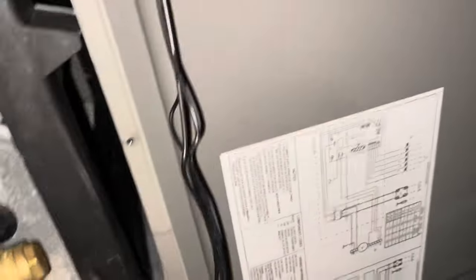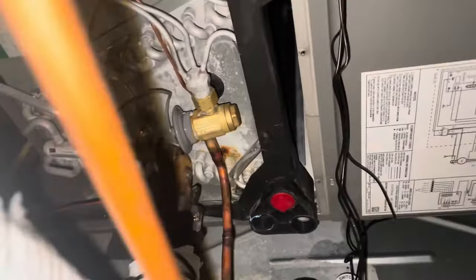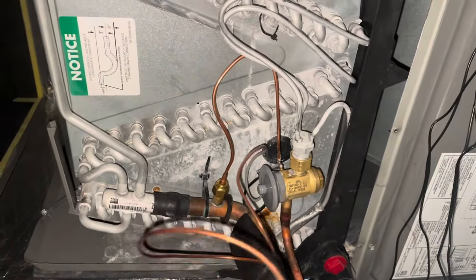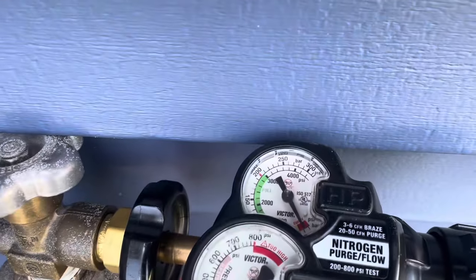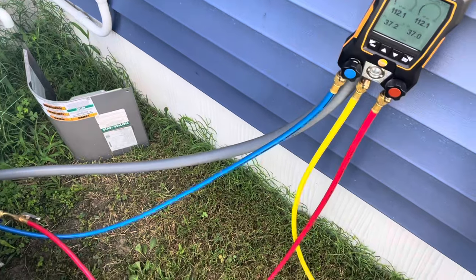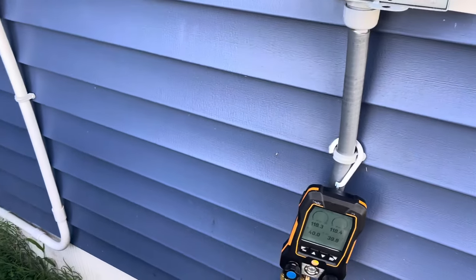We'll take our putty back off and get it mounted. We're brazed in, looks pretty good. Got this hooked up — we're gonna put it on pressure and make sure everything holds. Still gotta hook up the bulb. Pushing this back in there, securing everything, making sure it holds good. Putting pressure on her now — this tank's almost empty, we'll see what we can get in her. Should be enough to do a pressure test, hopefully 150 or so.